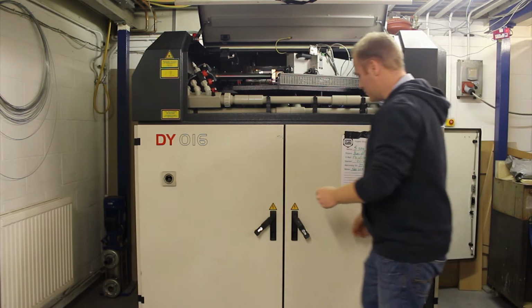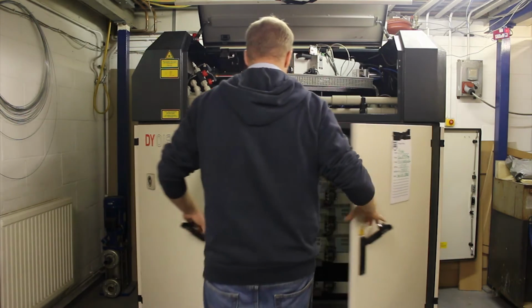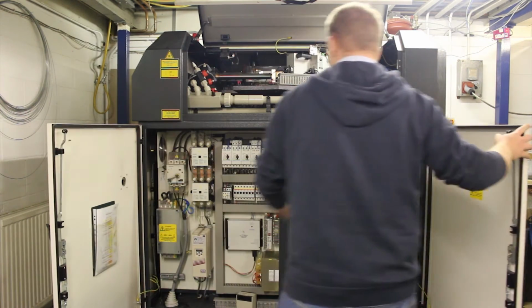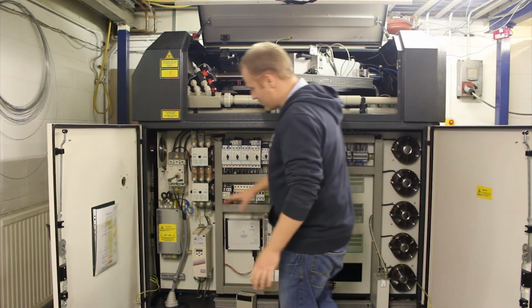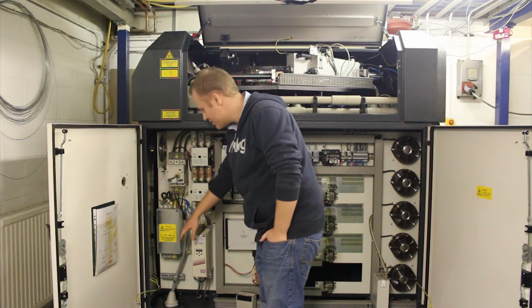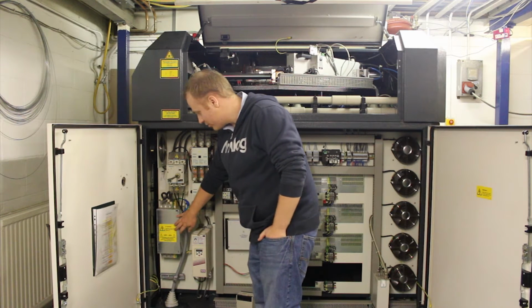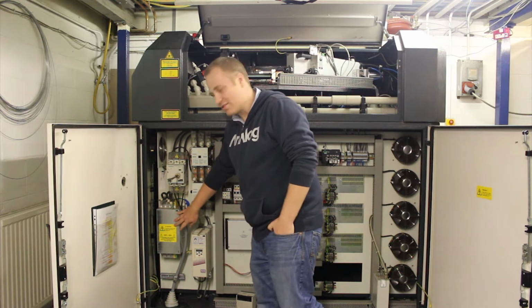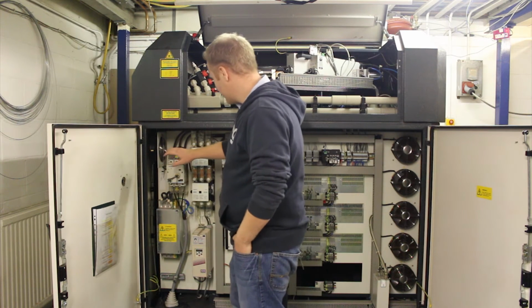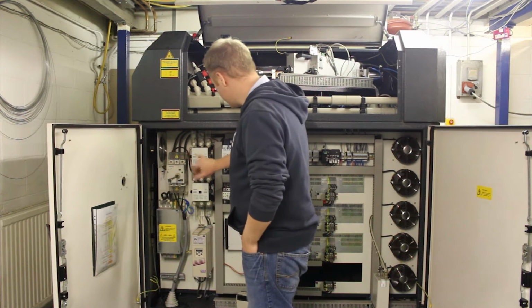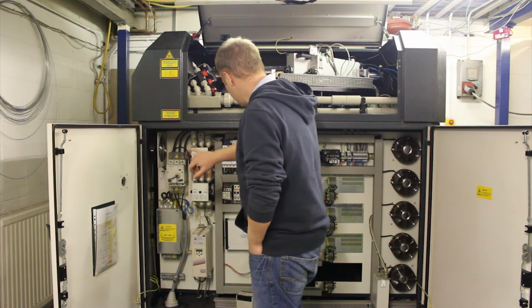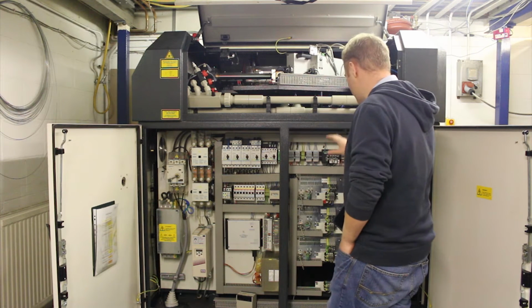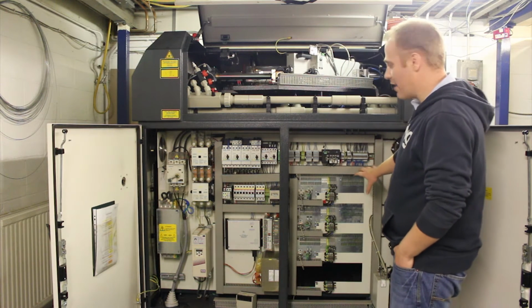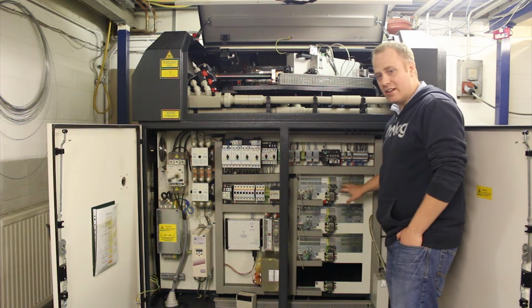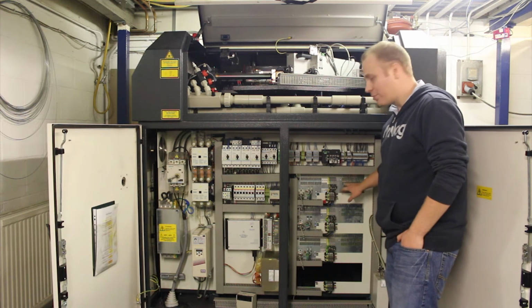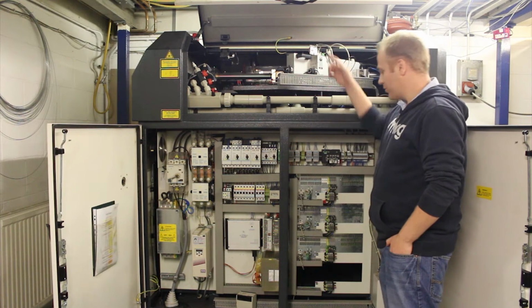If you open up the bottom, you can see a bit more. This is the control side of life. You've got a mains inlet here, where 63 amps of 3-phase comes in. There's a mains input filter which is currently bypassed to stop it tripping RCDs in the space. A big disconnect, then 2 contactors, and a whole bunch of mains control equipment to drive 3 big power supplies. These power supplies run the diode bars, providing very high current DC to the bars up top.